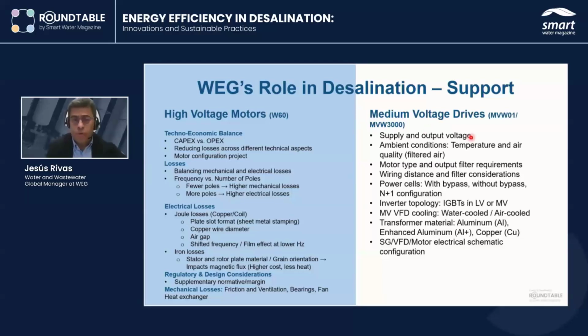And the same for the drives, the medium voltage drives. This is mandatory to consider that there is always going to be a medium voltage drive to drive this energy to the motor. And we have to consider in the electrical design of the whole plant the supply input and output voltages, the ambient condition where these drives are going to be located, the wiring distance between the drive and the motor. This is normally a big issue. This is not normally a big issue in the desalination plants because the distance is not so long, less than 500 meters. So maybe we don't have to put any filter or something like that, but in some cases it could be.